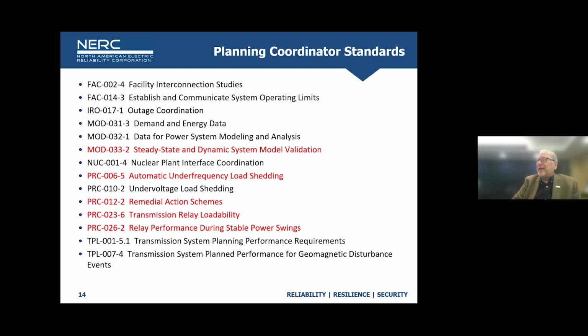So now the planning coordinator standards. Most of the standards also apply to the planning coordinator, but I've highlighted in red here some of the additional requirements that a planning coordinator has to do. They, in MOD 33, have to develop data validation processes for steady state and dynamic system model validations. In addition to under voltage load shedding, they're also responsible for automatic under frequency load shedding. So they have to develop a process to study those systems to make sure that they're coordinated. PRC 12 is remedial action schemes. So they're responsible for any type of systems that are automated systems that aren't necessarily protection, but might be generator scale back or sympathetic transfer schemes, so if a line is overloaded, it would do an automatic system to either back down generation or do some transfers on the transmission system to relieve that.